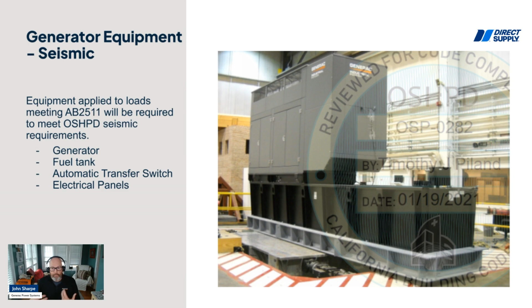What I'm showing you here is a 300 kW generator on probably a 48-hour tank. See how long that tank is to make 48 hours and stay under the footprint of the generator? That's on a shake table - a seismic shake table. That's one of our products that was seismically certified. So you can't just buy any generator and put it in there; we need to make sure it's seismically certified. And that means for 96-hour tanks, it's unlikely you're going to find one that fits under a generator and makes that happen. So recognize it's got to be seismically certified.